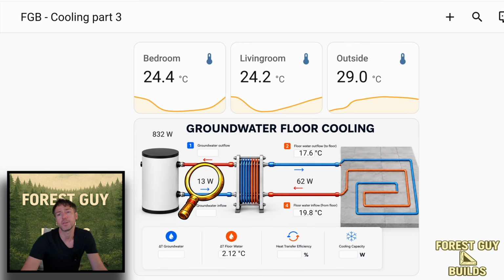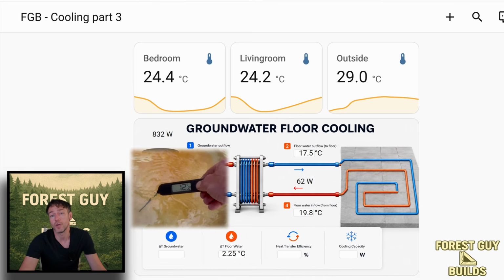On the groundwater side, the small low power pump is currently using around 14 watts, slowly moving groundwater from the buffer tank towards the heat exchanger. I don't have proper temperature sensors directly on both of the groundwater pipes at the heat exchanger, so those values aren't shown here. For now I measure the groundwater temperature outside in the buffer tank and in the return line.